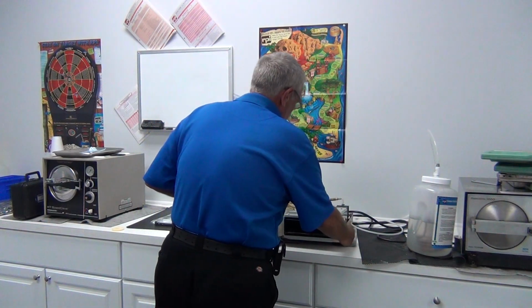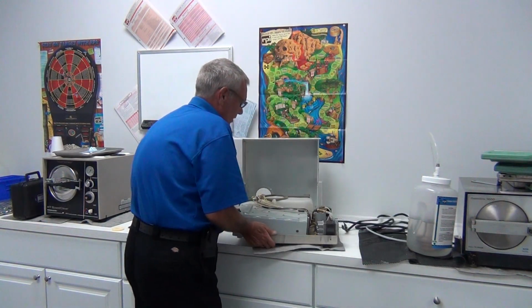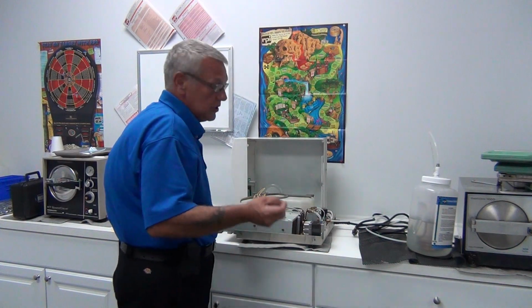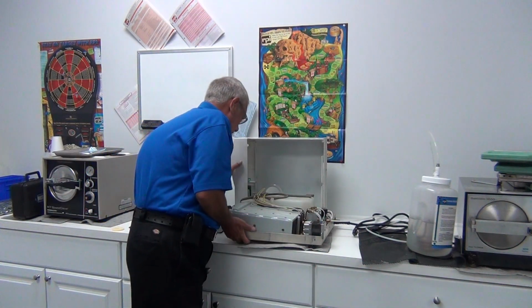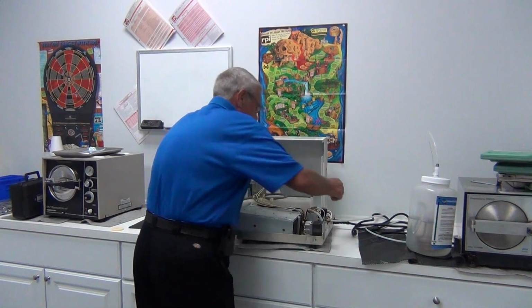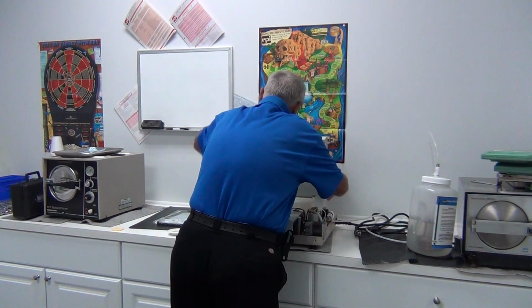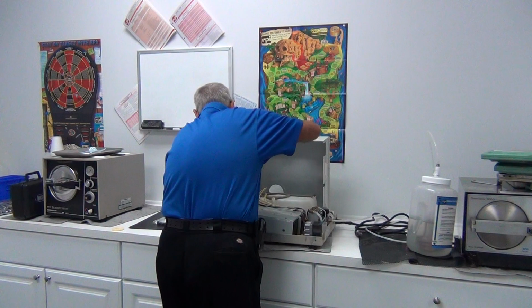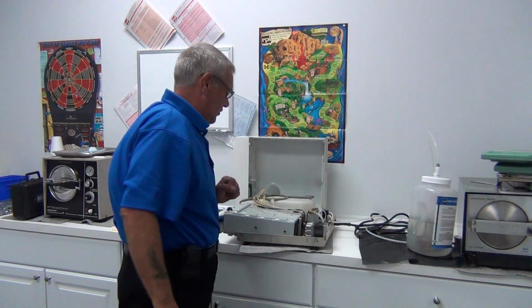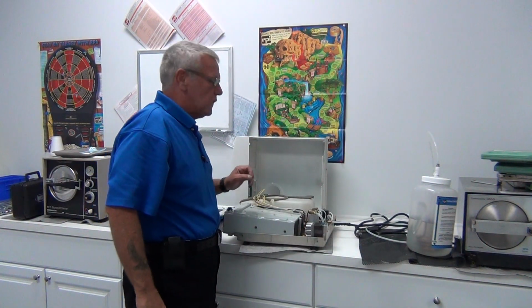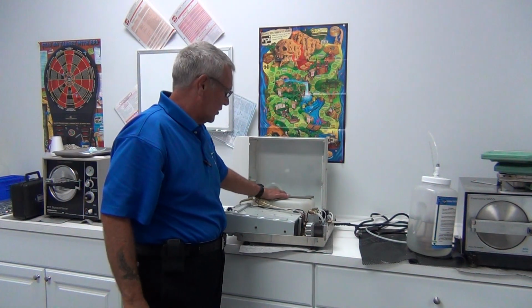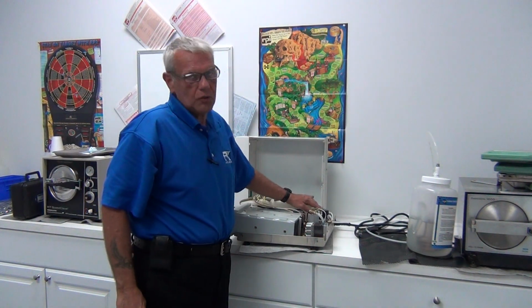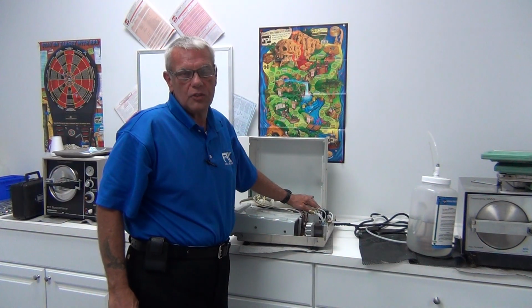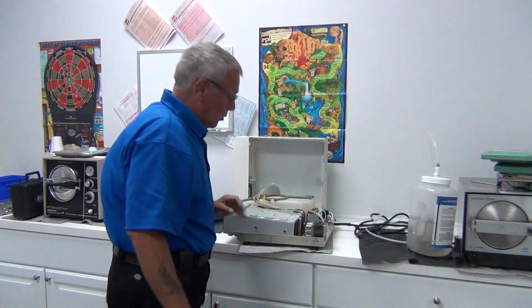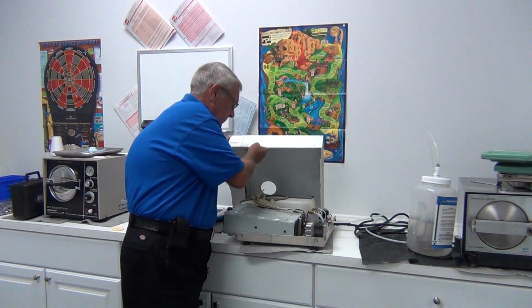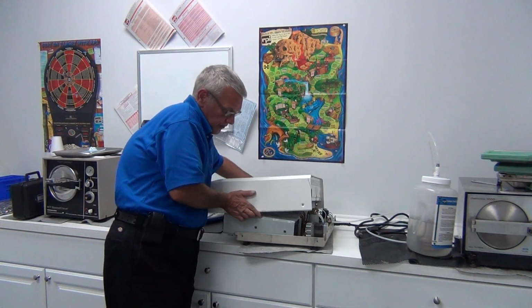Now, I'm going to turn the machine to its side to demonstrate how to put the covers back on, which was the same way that we took them off. But you can't be too careful doing this. Okay, we're going to take the cover out from under the legs of the body of the sterilizer, get some freedom of movement with it. We've already powered it down. Very important to power it down, guys. You have a circuit board over here and you have electrical components back here. If it's powered up and you short it out with that cover, more than likely it will blow the board. And that's not good when it can be prevented.